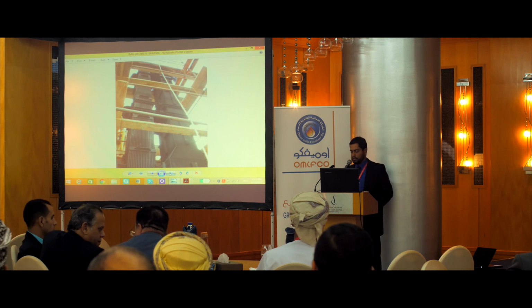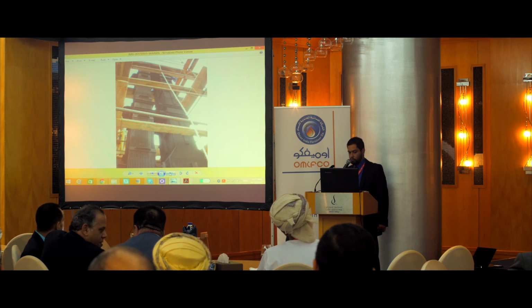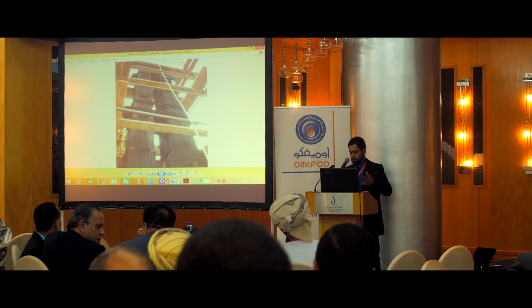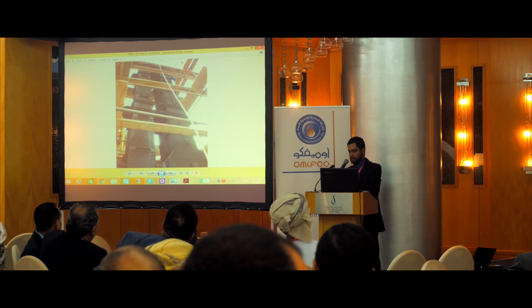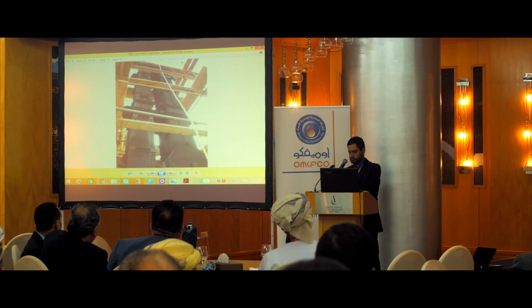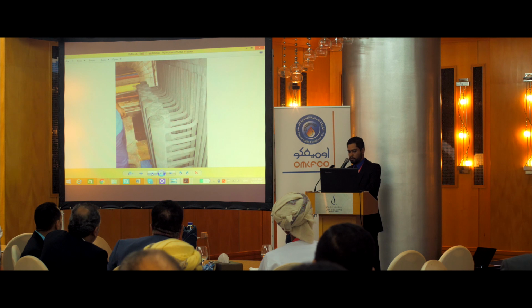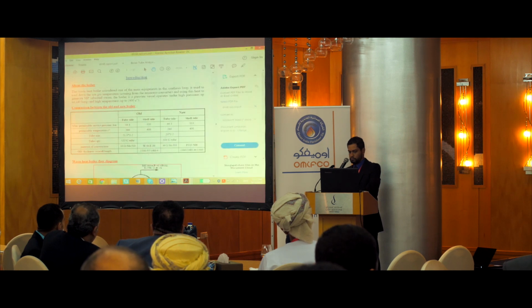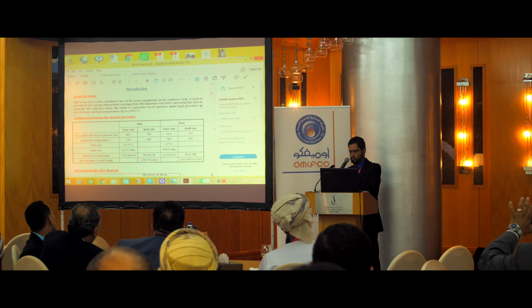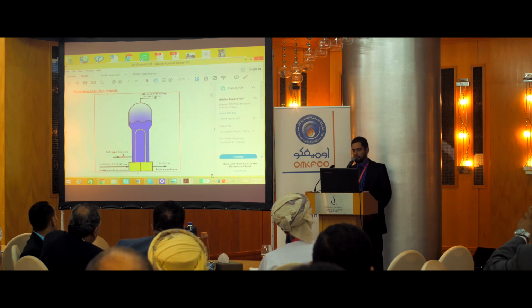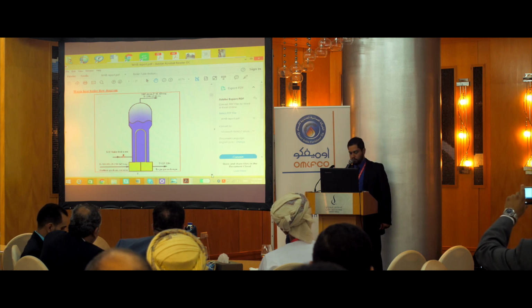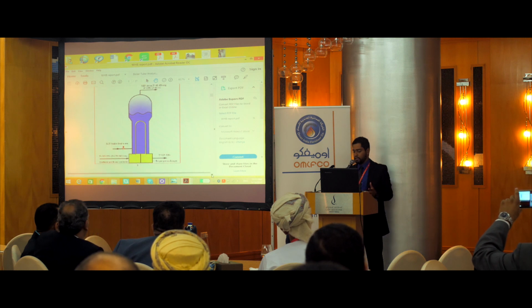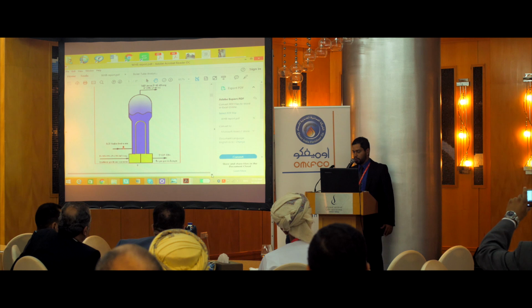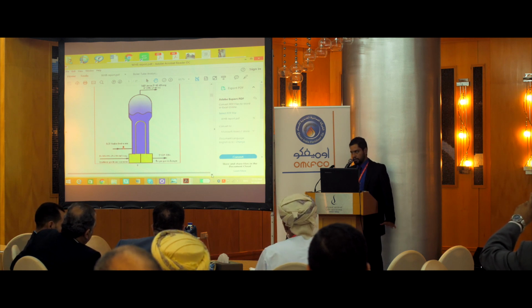There was a difficulty in plugging the tubes, and we lost a lot of tubes when we plugged the subheaders. Here are the headers of the waste heat boiler, the oldest type. The new type of the waste heat boiler is the fountain type. It was very easy to do the pressure test and to plug tubes, and till now there has been no leakage and no problems.